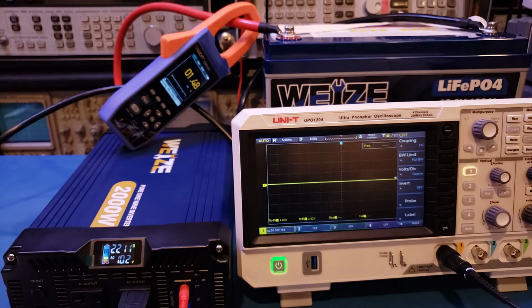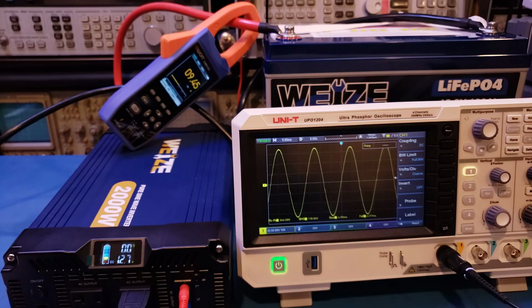At around 2200 watts, you can see we're now oscillating, and the inverter actually shuts off—that's expected behavior. Let me change it to 2000 watts so the inverter does not shut off. I don't quite like this shut-off behavior, because it shuts off, and then when the power draw drops below 2000 watts, it starts back up again, which causes some oscillation in the output.